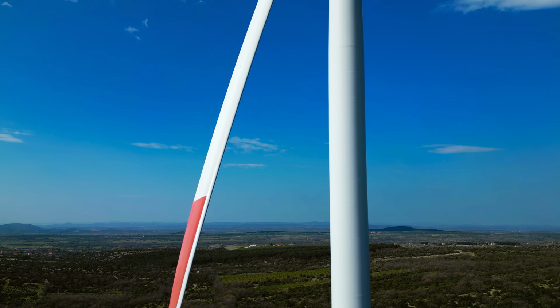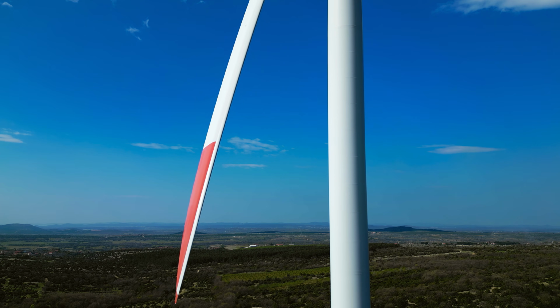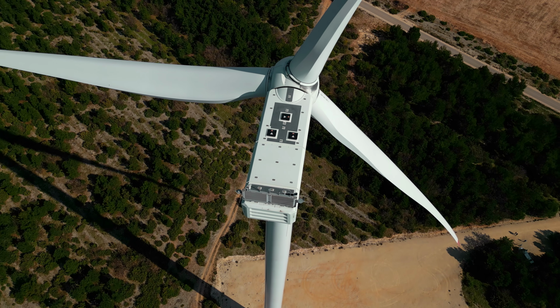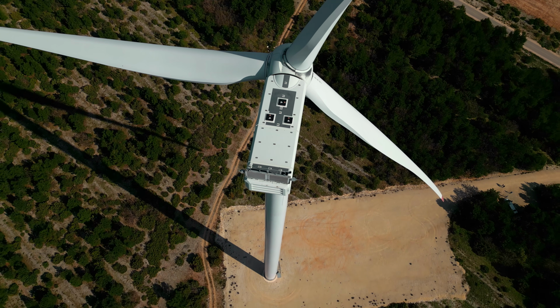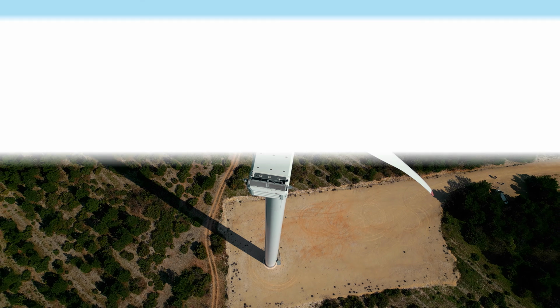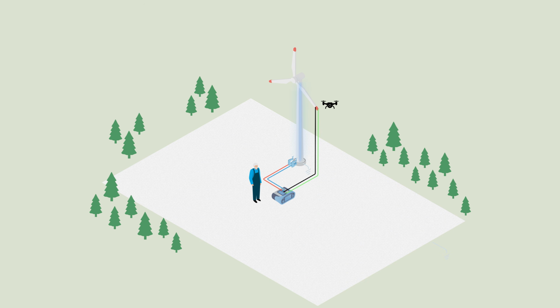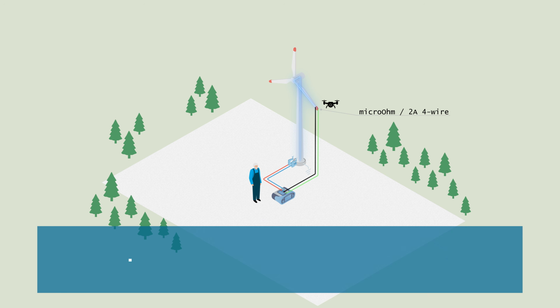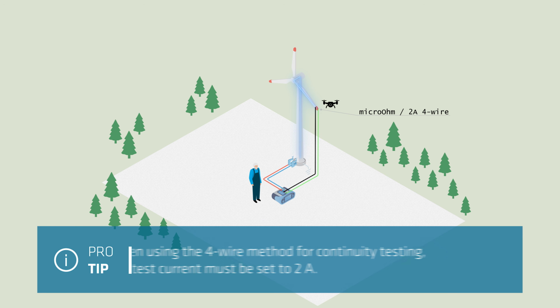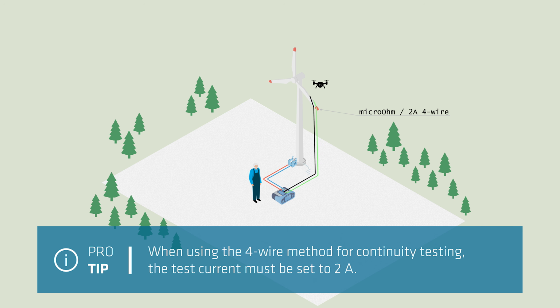This method is particularly useful because from the blade tip to the foundation, every part of the turbine must be properly electrically bonded and tested. The process begins with testing the down conductor cables. The down conductor is a crucial component in the lightning protection of wind turbine blades and must be thoroughly tested to ensure good continuity and the ability to direct lightning energy into the ground.